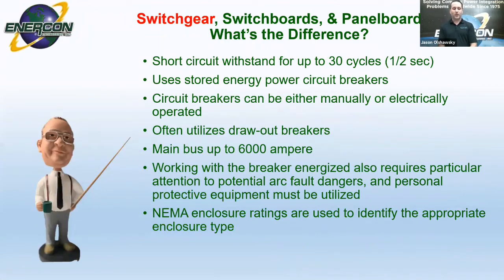All switchgear will have a short circuit withstand rating, and this is based on a time frame of up to 30 cycles or half a second. It is the amount of short circuit fault current that the mechanical assembly, electrical bus, and bracing can endure for 30 cycles without sustaining damage at that particular tested voltage, and that really defines what we're describing here as far as short circuit withstand rating.